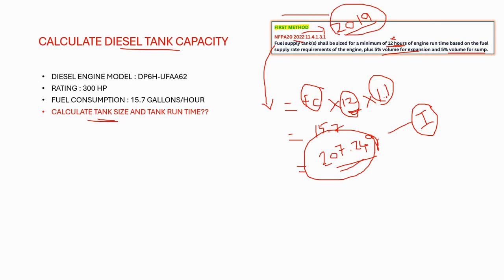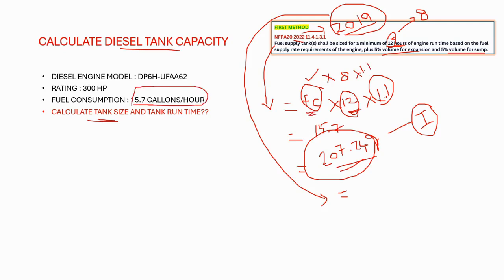Now we will calculate using the 2019 edition. As per the 2019 edition, the 12 hours is changed to 8 hours. So: fuel consumption 15.7 × 8 × 1.1 = approximately 138 gallons. Which edition you need to consider depends upon the project specification requirements — you need to select the tank accordingly.